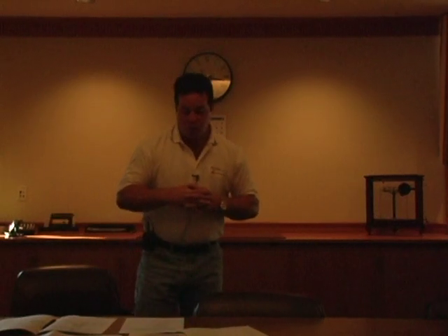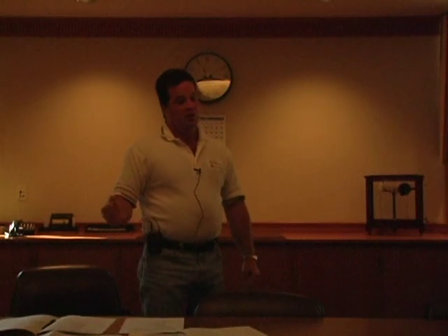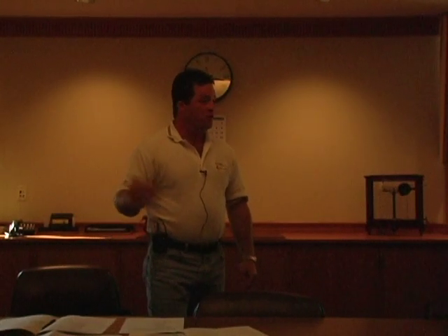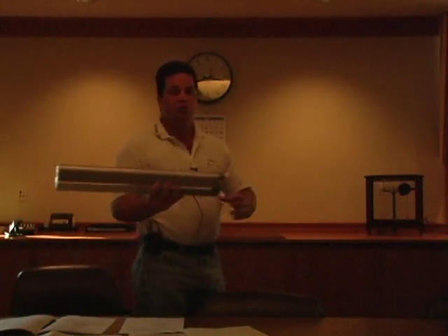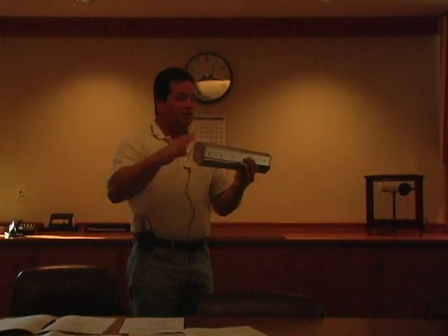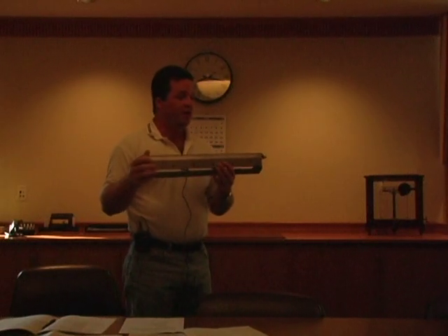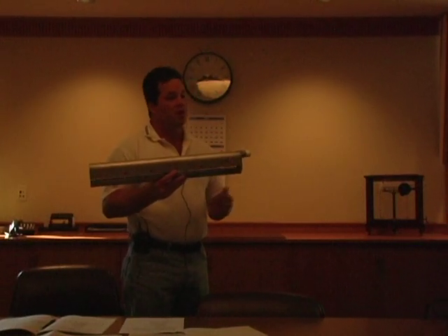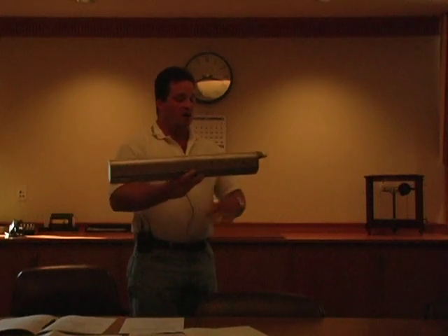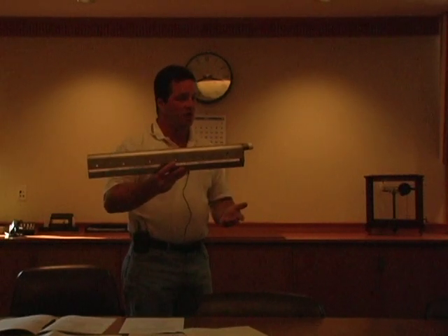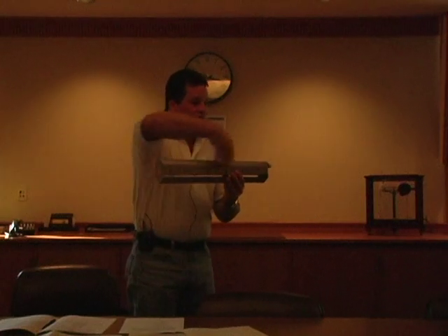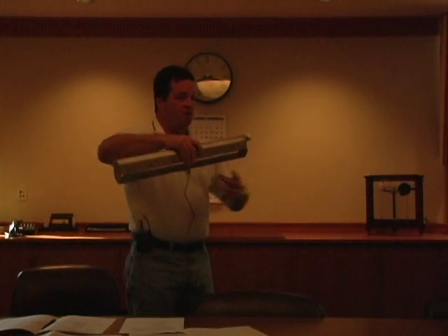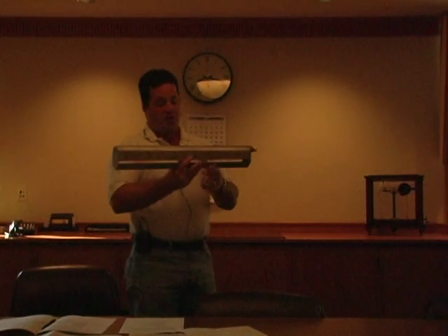I'll get into a little bit of the preventative maintenance. What Sanitary suggests is once a year that we take down these tanks and basically just wash with a 1-inch fire hose. These are considered a non-clogging diffuser, and they have been in service for many, many years without any preventative cleanings, but we recommend that you take down the tank itself, bring it below the manifold and diffuser elements, hose out any rags or anything that might be caught or hung up around the diffuser itself, and just clean it up.